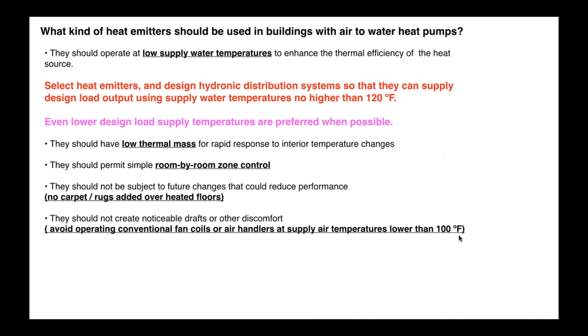Okay, I also like room by room zone control. It's one of the distinct advantages or benefits of hydronics. It's very easy to do that. If you are doing floor heating, you really want to stay away from large area rugs or carpet and padding that obviously forces that water temperature up and penalizes the performance of the heat pump.